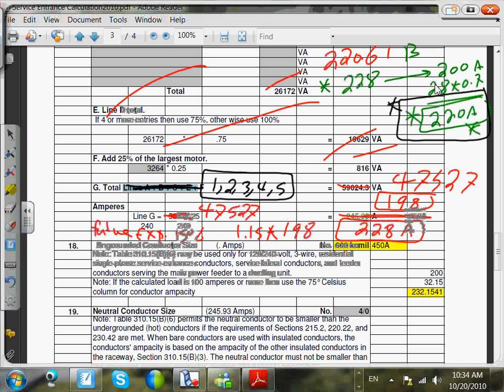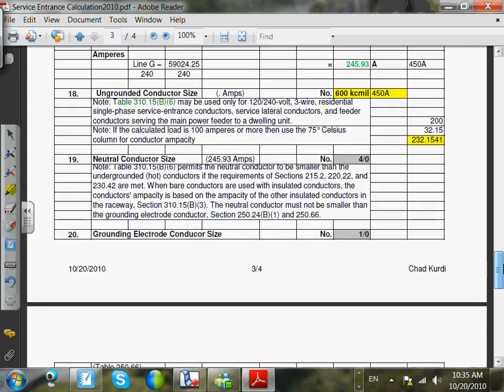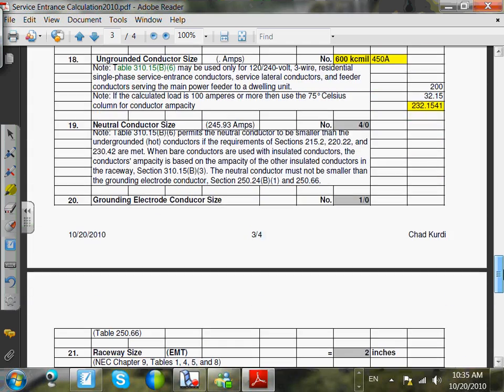I want somebody, guys, to remind me. We came up, what's the size of the panel that we came up with? 500 amp panel. And what's the neutral? 220. Okay, I'm going to go back and size the cables now. All the way to the cable. That's it, done. I promise. Now, we're going to go to the table.